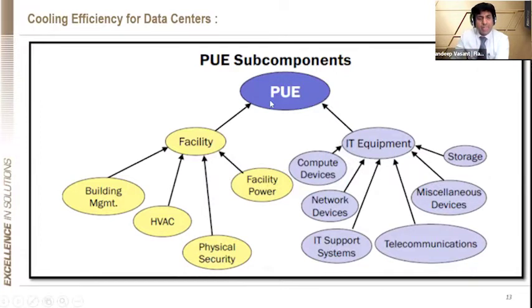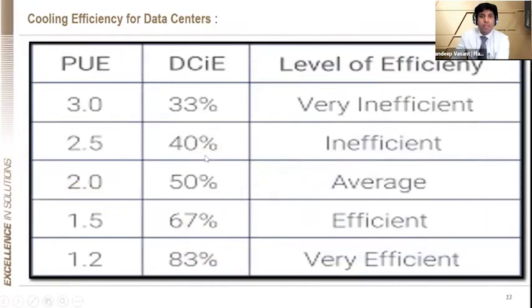center, the metric or the language is the PUE, power usage effectiveness, which is the power consumed by the facility, where you have the HVAC as well, divided by the IT equipment. As I said in the previous slide, 30 plus 8, 38% is the power consumption. We would be focusing more on the HVAC today. On the PUE, just for everyone's benefit, the PUE numbers range from 3 down to 1.2. 3 means very inefficient, 1.2 means very efficient. The global average, as per the Uptime Institute, is around 1.55. Again, it depends upon the type of data center, server, location, heat load, and various other parameters.